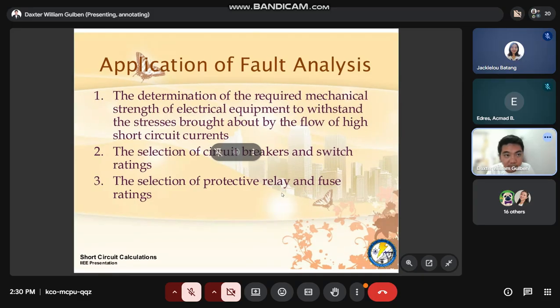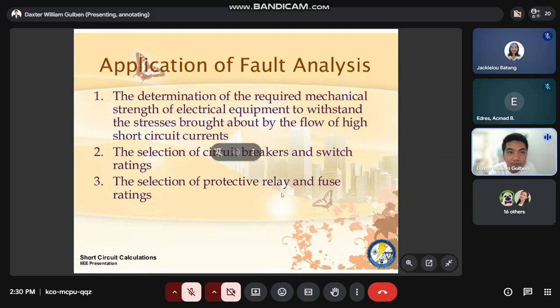Okay? So there are a lot of applications in the short circuit analysis, or what we call a fault analysis. So once we know or determine the fault current, the fault voltage, the fault impedance, the fault MVA, we have a lot of applications. Number one, we can determine the required mechanical strength of electrical equipment to withstand the stress brought about by the flow of high short circuit currents.